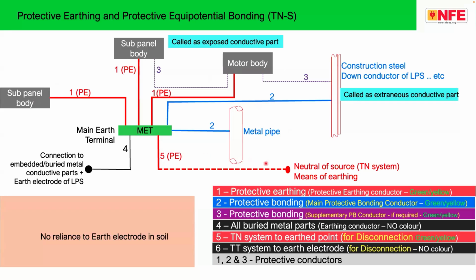Now the MET has to be connected to the neutral of the source. This is a TN-S system and this is earthing. As I put here, no reliance on an earth electrode in soil in the case of a TN-S system. And we are supposed to follow a TN-S system in a medical facility because today's biomedical equipment is demanding a TN-S system. Please note, earthing has nothing to do with an earth electrode. Earthing is a safety measure with which potential differences, voltage differences within a building, are limited by bonding conductive parts to a common bus bar. This is earthing.